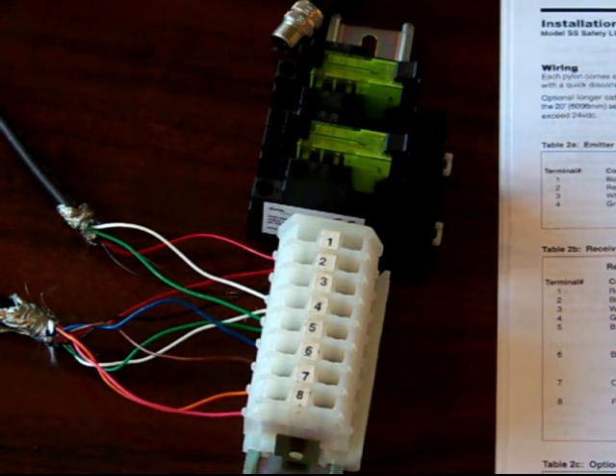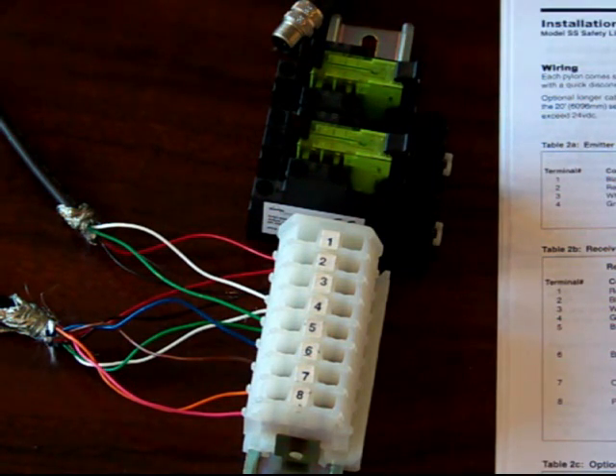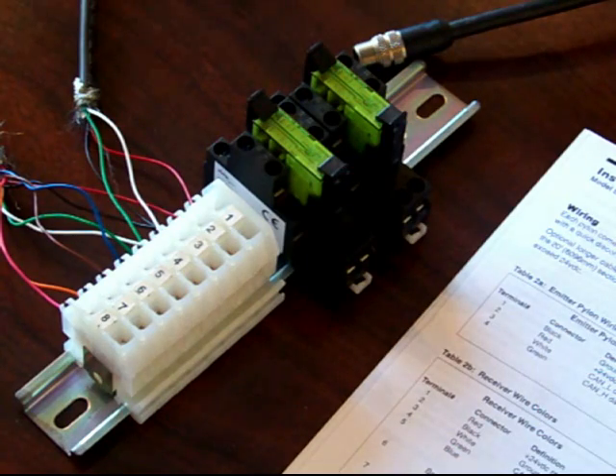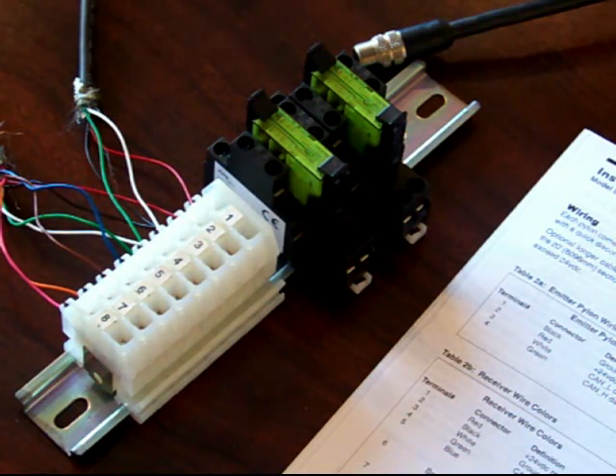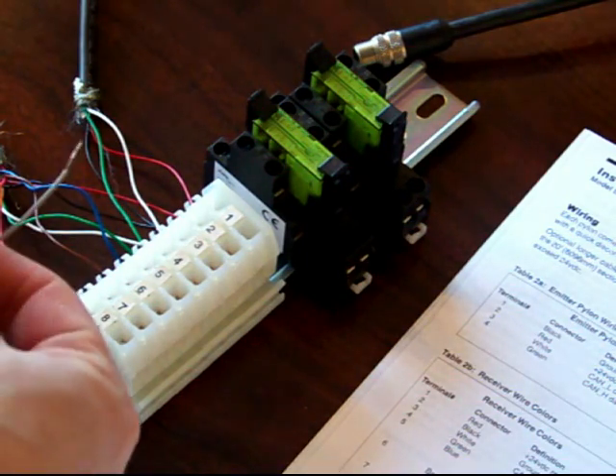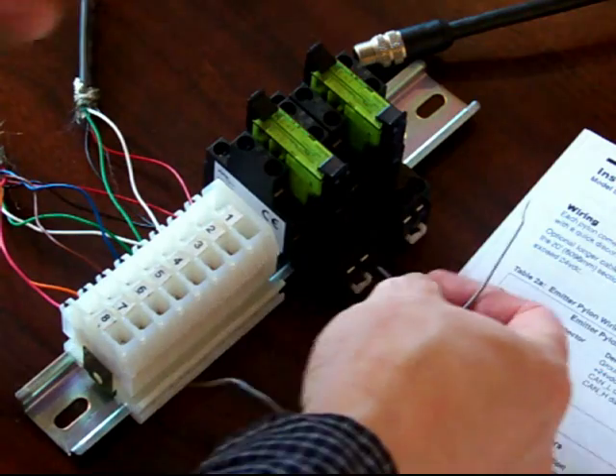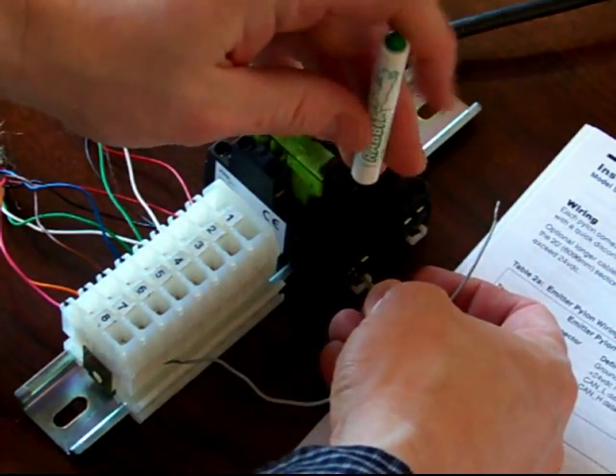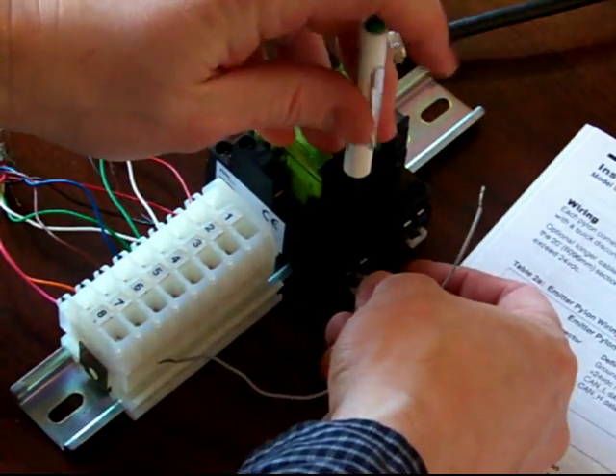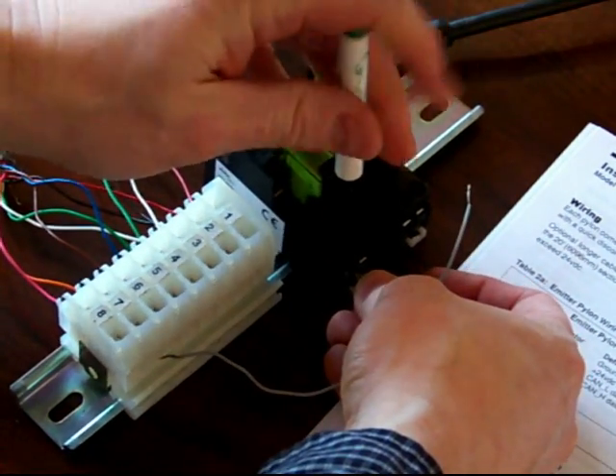The next step is to wire the two safety relays to the terminal strip. According to page A11, the terminals A1 on both relays get wired together and then over to ground, which is terminal 2.